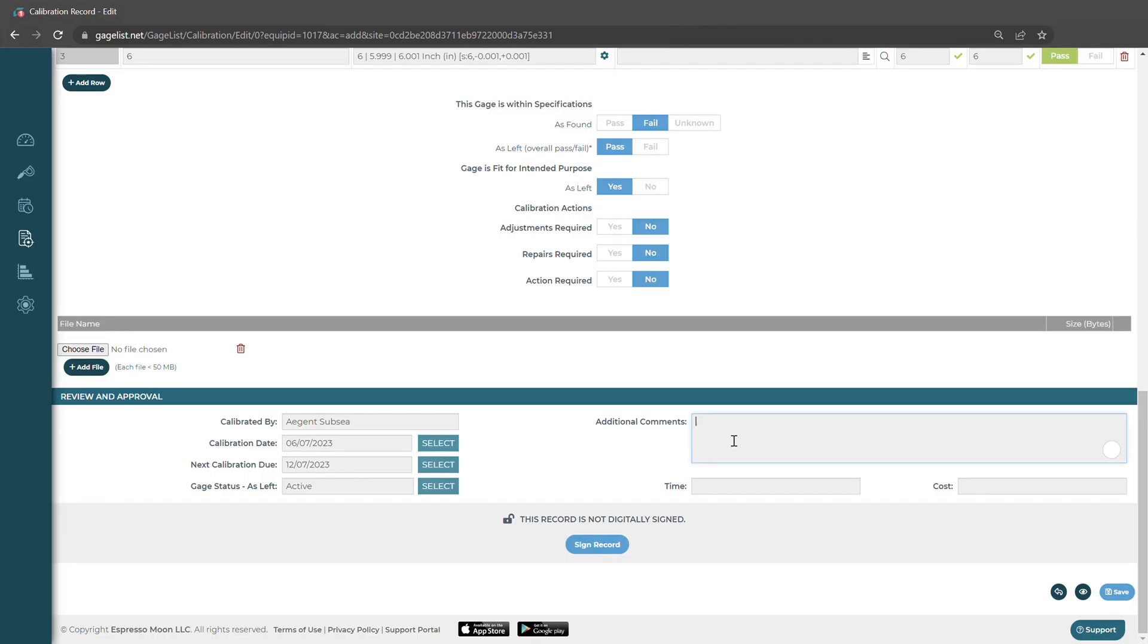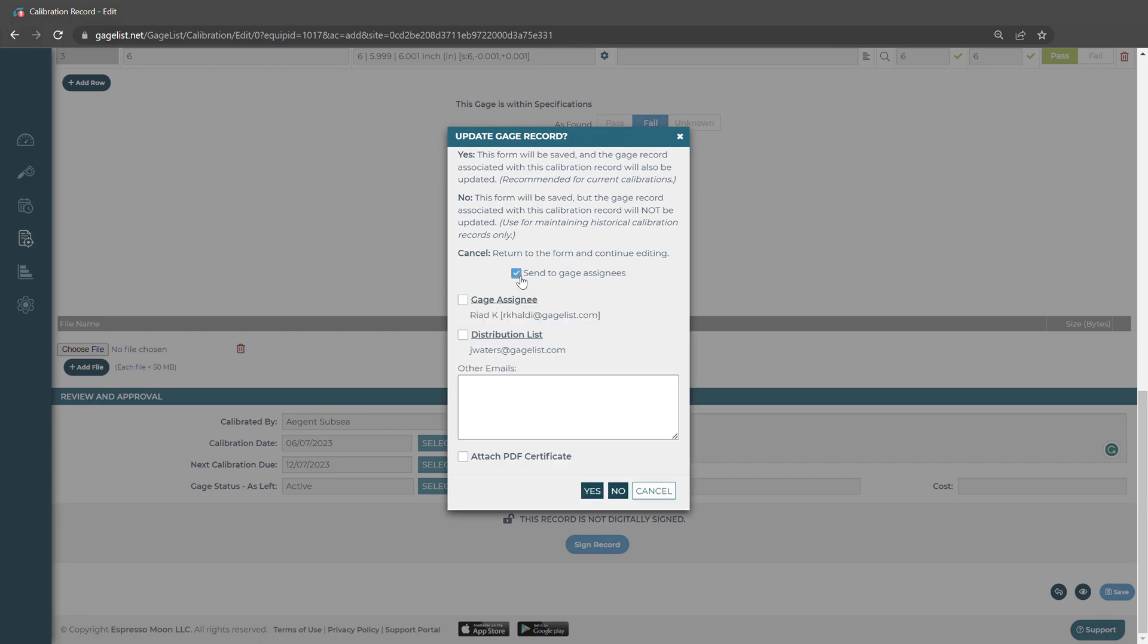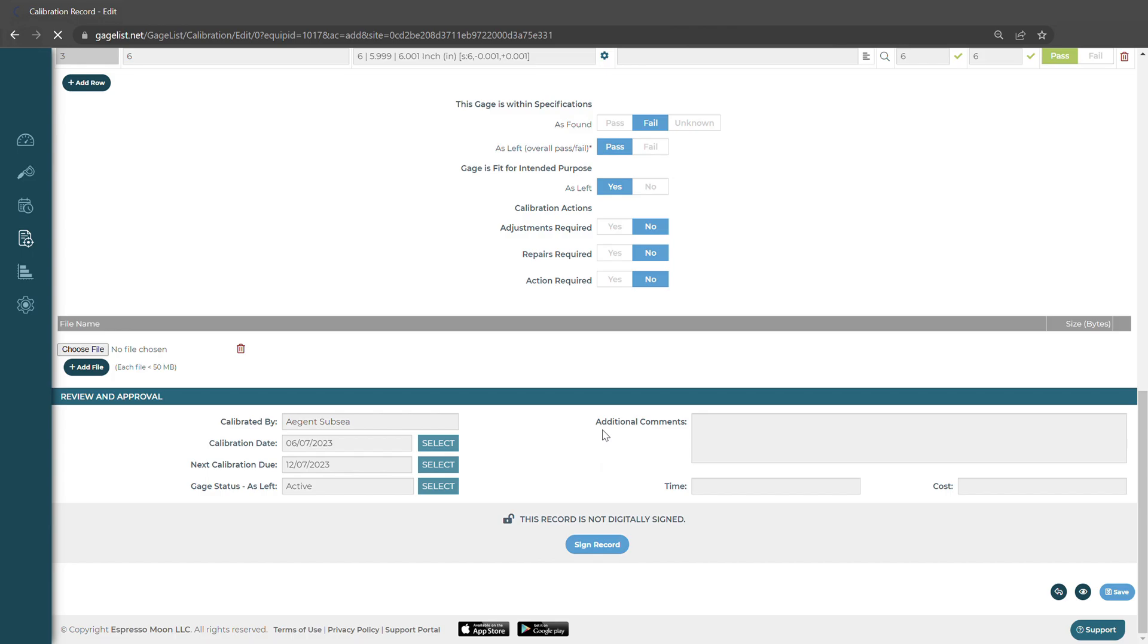We can record any additional comments or time and cost. And then we could save the record. It'll ask us if we want to update the gauge record. We're going to want to select Yes because this will update the last and next calibration due dates on our gauge record. We can also choose to send a notification to our assignees and we can include the PDF attachment to be sent. We'll select Yes.